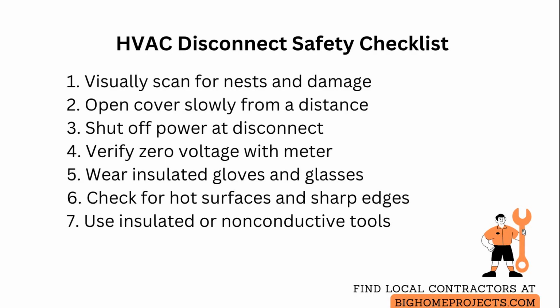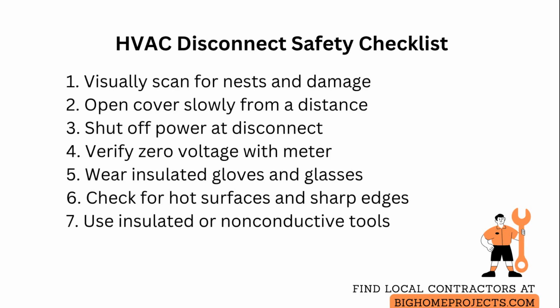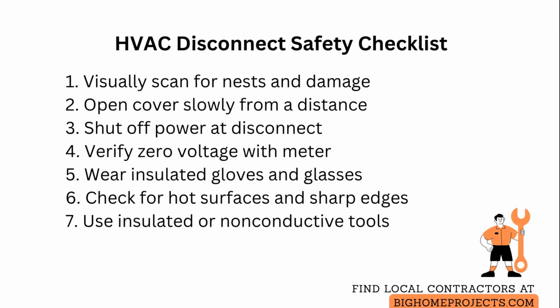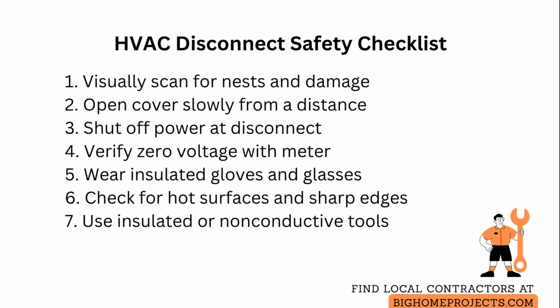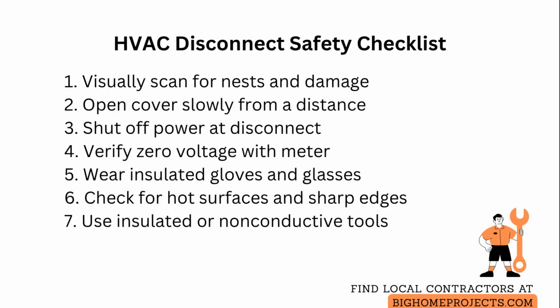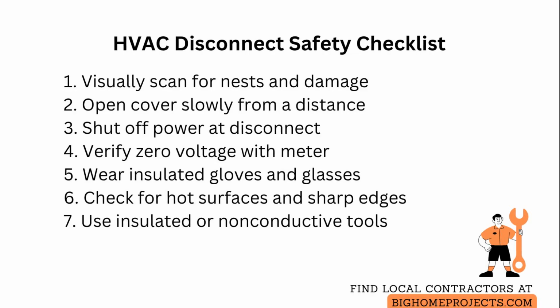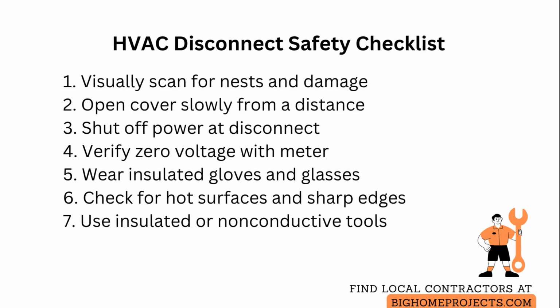Shut off power at the disconnect and verify zero voltage with a reliable meter, following test meter verification procedures by testing a known live source first, then the target, then the known live again, so you never trust a single reading. Wear insulated gloves sized for dexterity and rated for the system voltage, along with safety glasses or a face shield to protect against arc flash and flying debris.